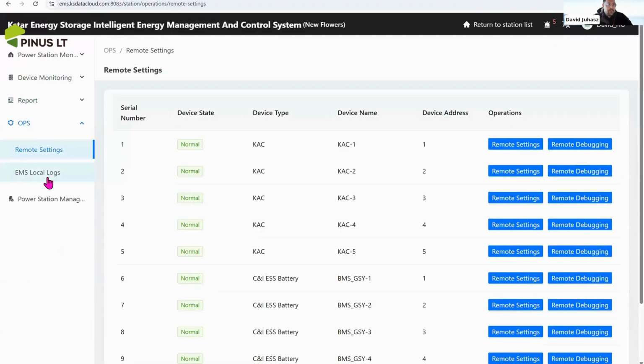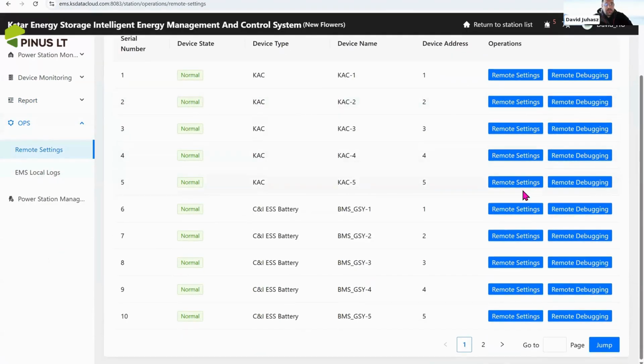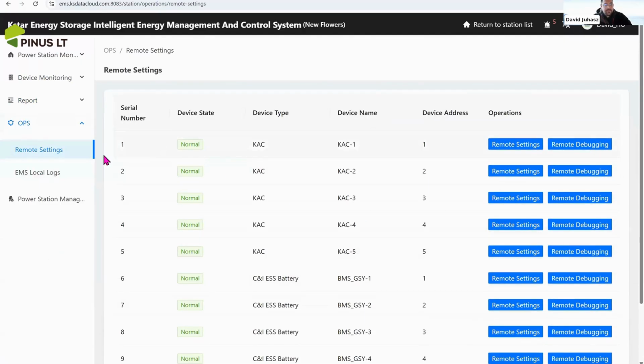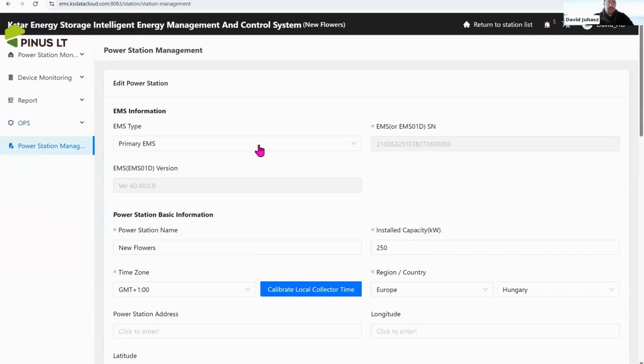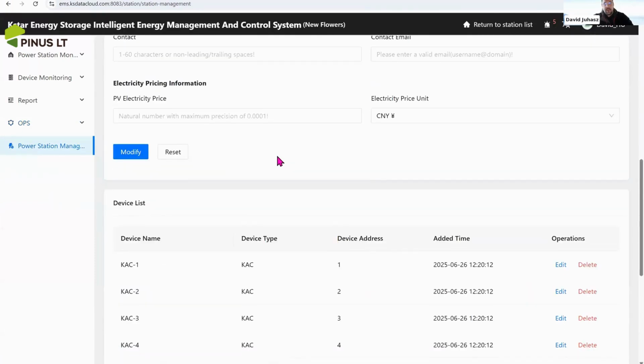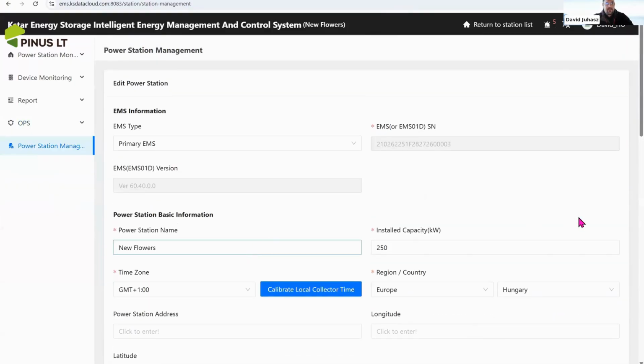For example, remote settings of each inverter one by one or battery cabinets. You can adjust the protection parameter or anything that is necessary to make the smooth working. And lastly, we can see here the main parameters of the site, which need to be given during the first commissioning.